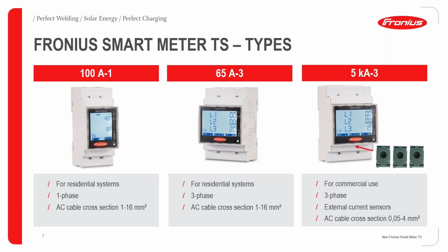Then the categories: 100A1 is the single phase for residential systems. I believe in our market, the Nordics, we do not have many single phase systems, so we will go directly to the 3-phase systems. The second one is the 65A3, and the third one is the 5KA3. The technical specification is the same as the previous versions, like the 65 amps and the 5 kiloamps. Both of them are 3-phase, and the AC cable cross section for the 65A3 is 1 to 16 square millimeter. But in the 5KA3, the cross section is smaller because you need one lead to measure the voltage, because you are going to use external current sensors in this 5KA3 smart meter.